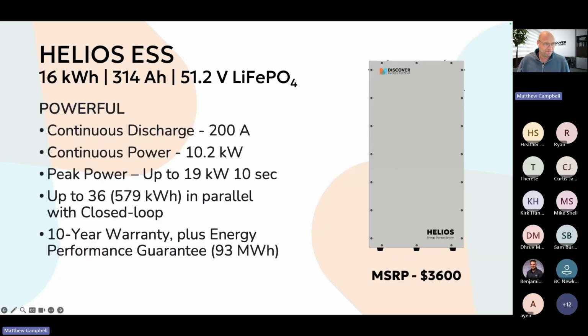Getting into some of the specs, it's a very powerful battery. You have a continuous discharge of 200 amps, your continuous power is 10.2 kilowatts, and we can surge for 10 seconds up to 19 kilowatts, so it has a very large surge. What's really great is that, much like our rack-mounted batteries, you can parallel in closed loop up to 36 of these together to get a very large system. I think I have a typo there - it should be, well, it's 578.8, round up to 579 kilowatt hour.